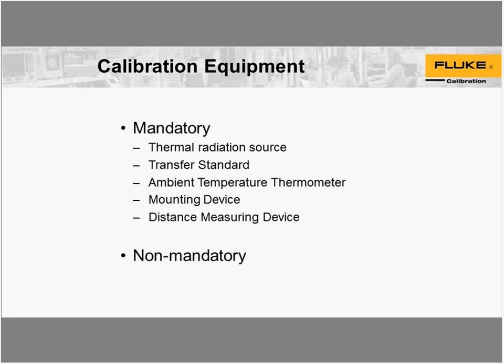What we need for calibration — there's some equipment that's mandatory, and we'll talk about that in the following slides. Some of the mandatory equipment includes a thermal radiation source, a transfer standard, a thermometer, a mounting device, and a distance measuring device. There is also non-mandatory equipment.